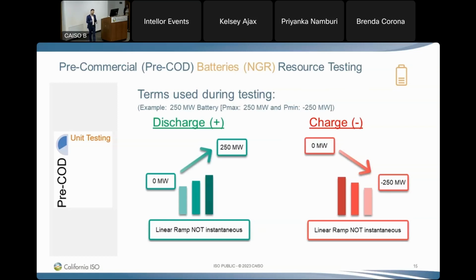We actually had an instance where we had a battery down in Southern California start to oscillate, meaning rapid, uncontrollable movement, 0 to 100 as fast as it could go. With inverter-based generation, it's extremely quick. That was seen across the whole Western interconnection. Entities up in the Northwest started taking mitigation actions. So when I called the scheduling coordinator to report what they just did, there was an odd silence on the phone when I said, you just caused this, we need you to come offline immediately. They said, well, why? Reliability. They said, well, why? It's like, you just caused a WECC-wide disturbance. And immediately that resource got offline.